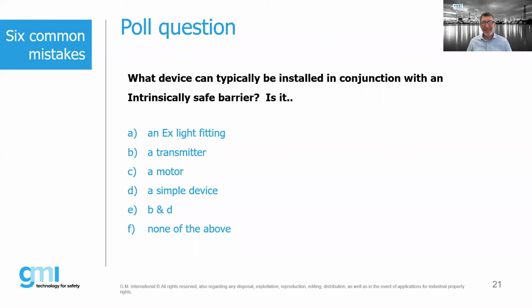So for an Ex light fitting, generally speaking, the power that will actually be allowed through, based upon the ignition curves for intrinsic safety, is about 1 watt. So we're way below the power that we would need to operate either a motor or an Ex light fitting. But certainly things like a transmitter or a simple device, absolutely, we can use intrinsic safety. It's not the only method, but certainly those are prime examples of types of devices that can be made intrinsically safe.